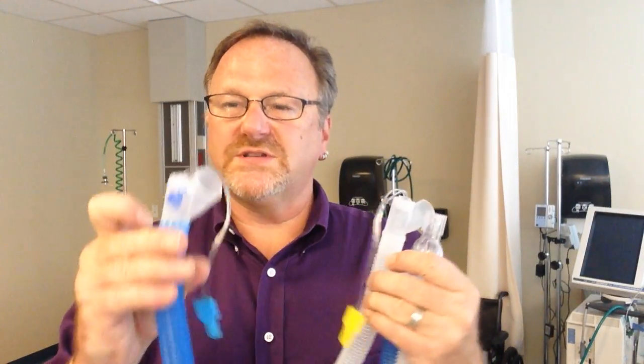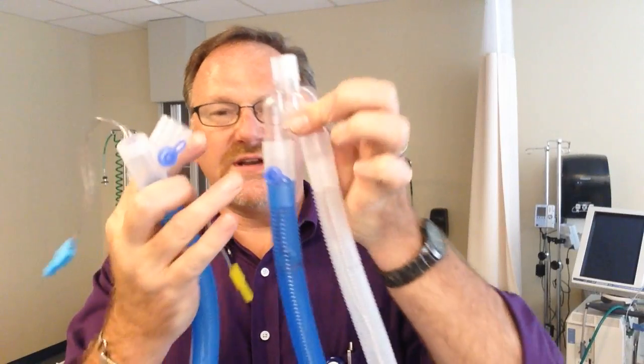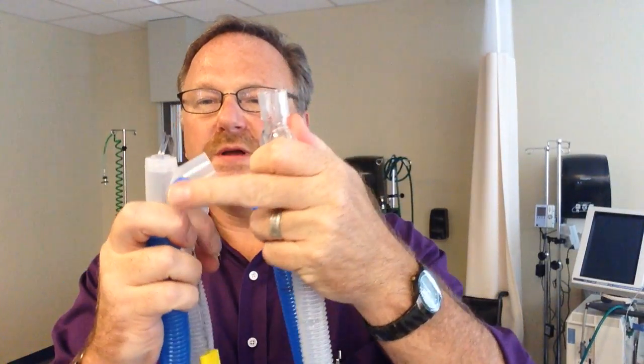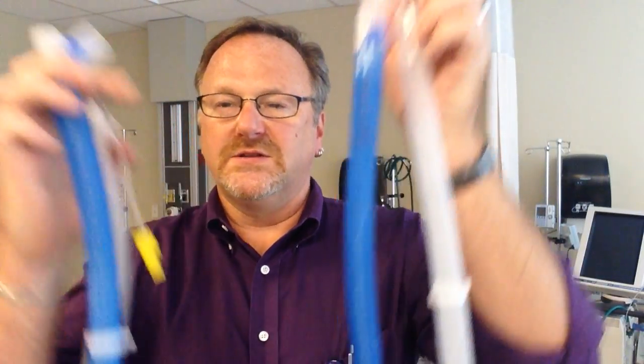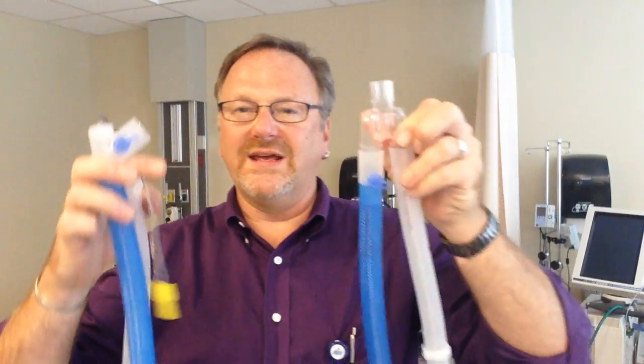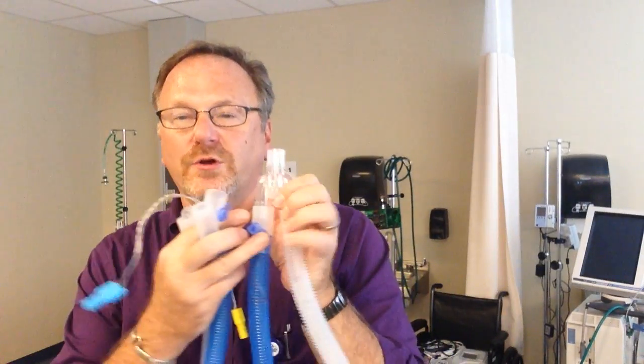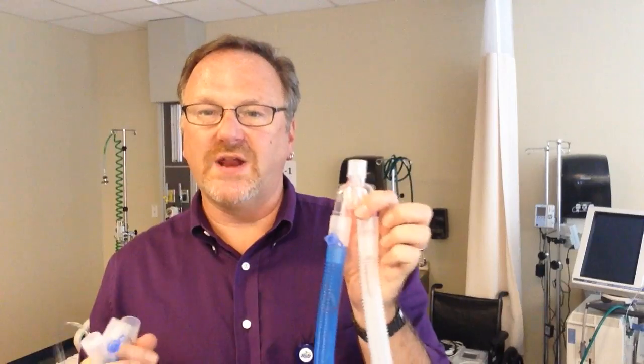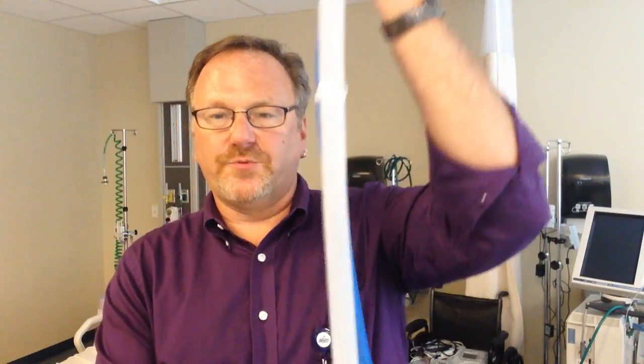We have an inspiratory side. How can I tell this is the inspiratory side? I have a temperature probe. So on this one, blue is the inspiratory side. Now I don't want to hear, well, which side's inspiratory? The blue side. No, you look for the temperature probe. That's how you can absolutely tell. There are no temperature probes on the exhalation side. We have the temperature probe so we do not burn our patient's airway.